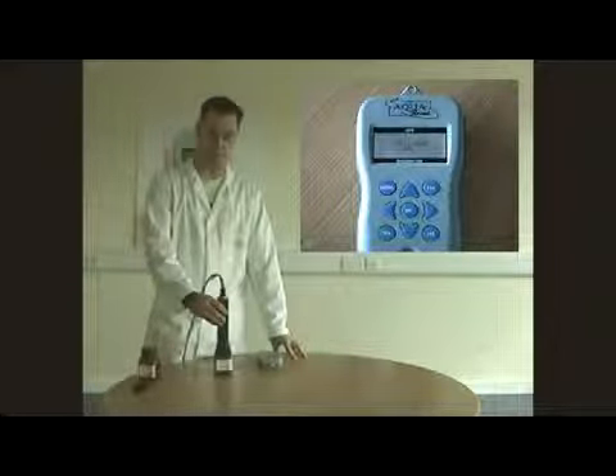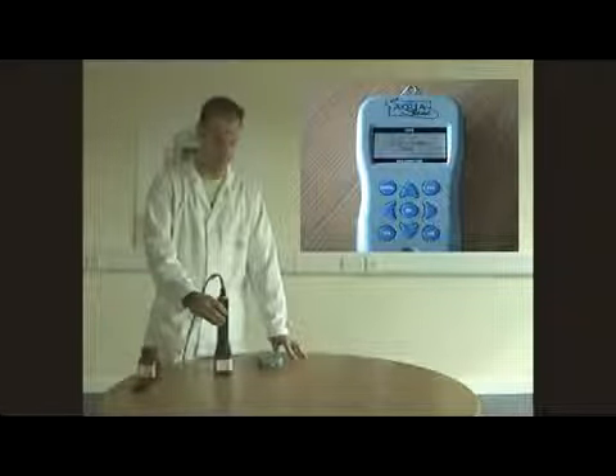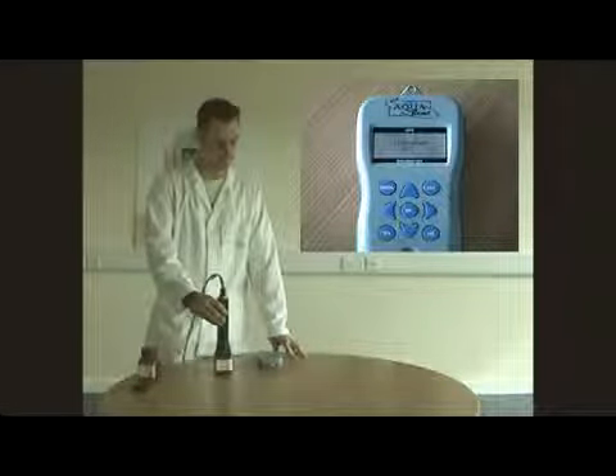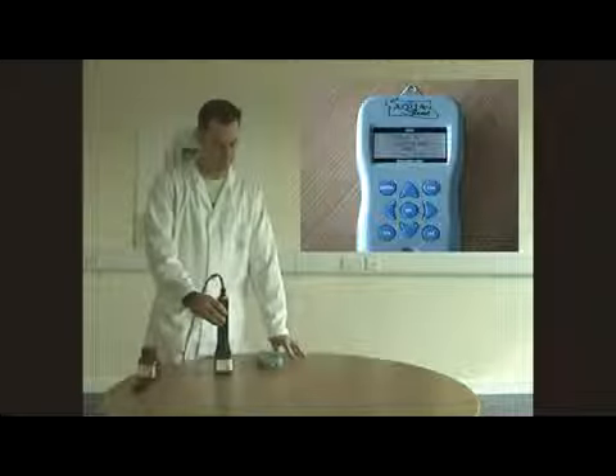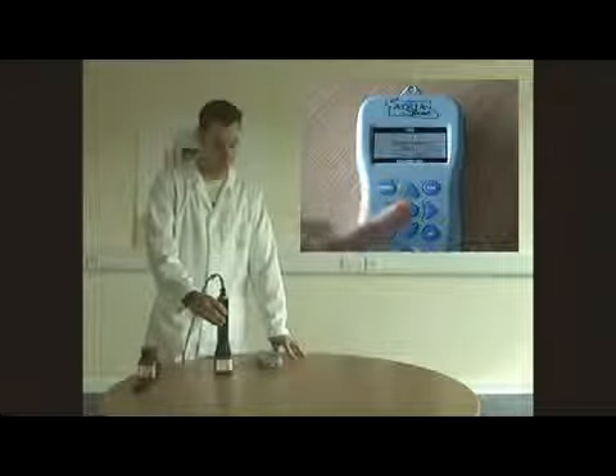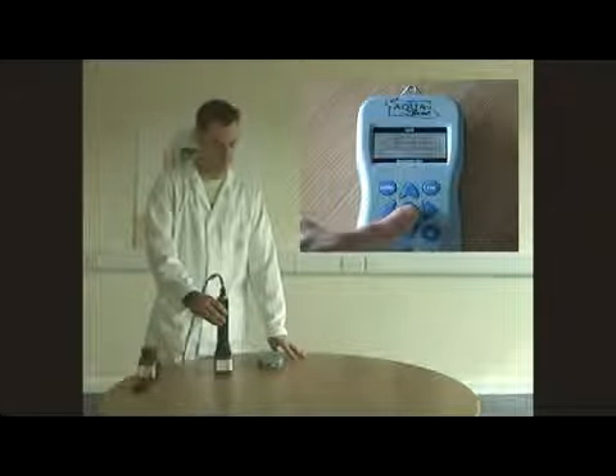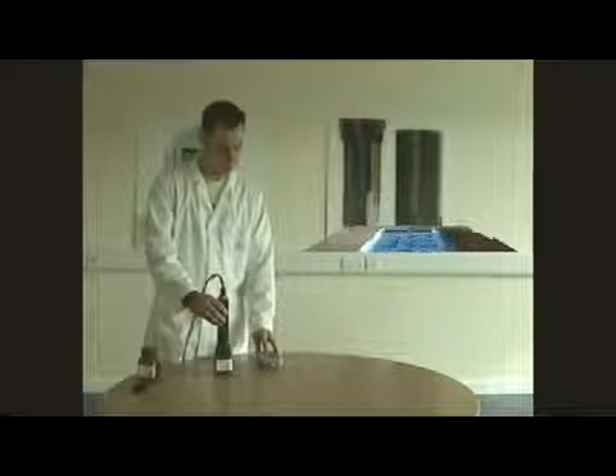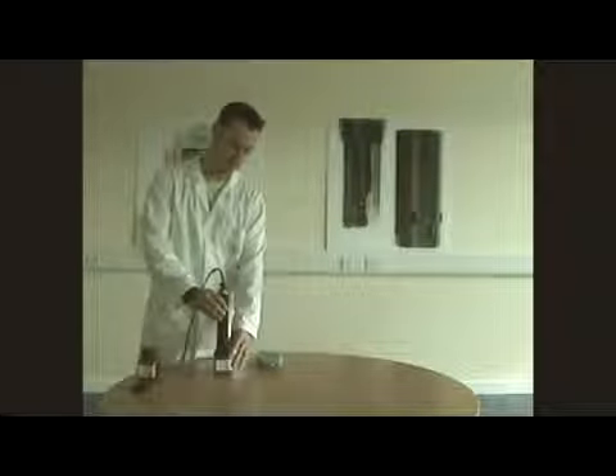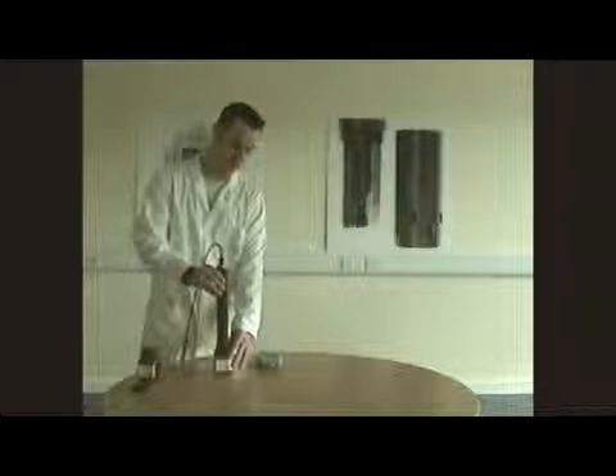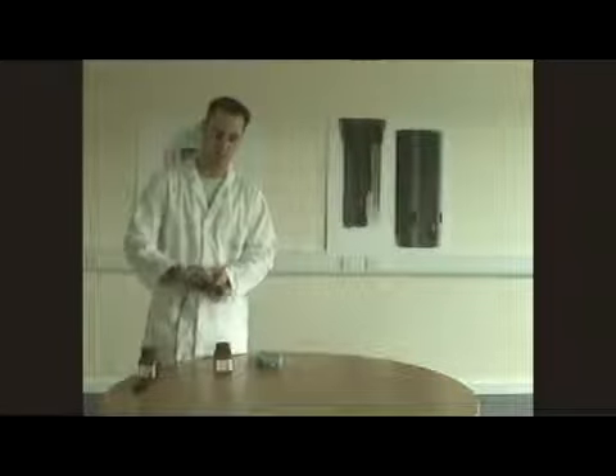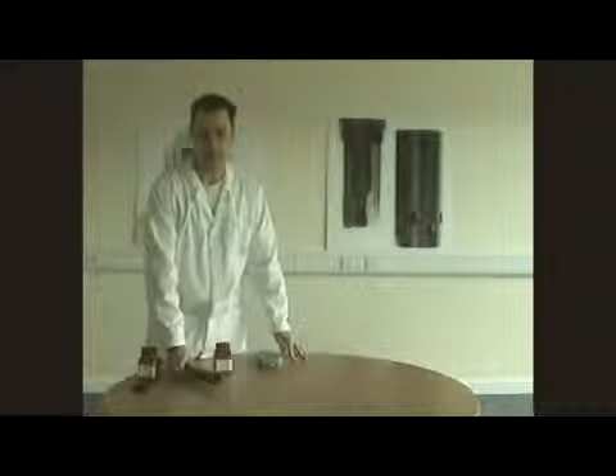Again, allow a little time for this. If your bottles have come out of the fridge, this can take a little longer. There we go, calibration has begun now. Okay, that's it. Calibration at pH 4.01 complete. We now have our 2-point calibration for pH and should be able to achieve accurate readings.